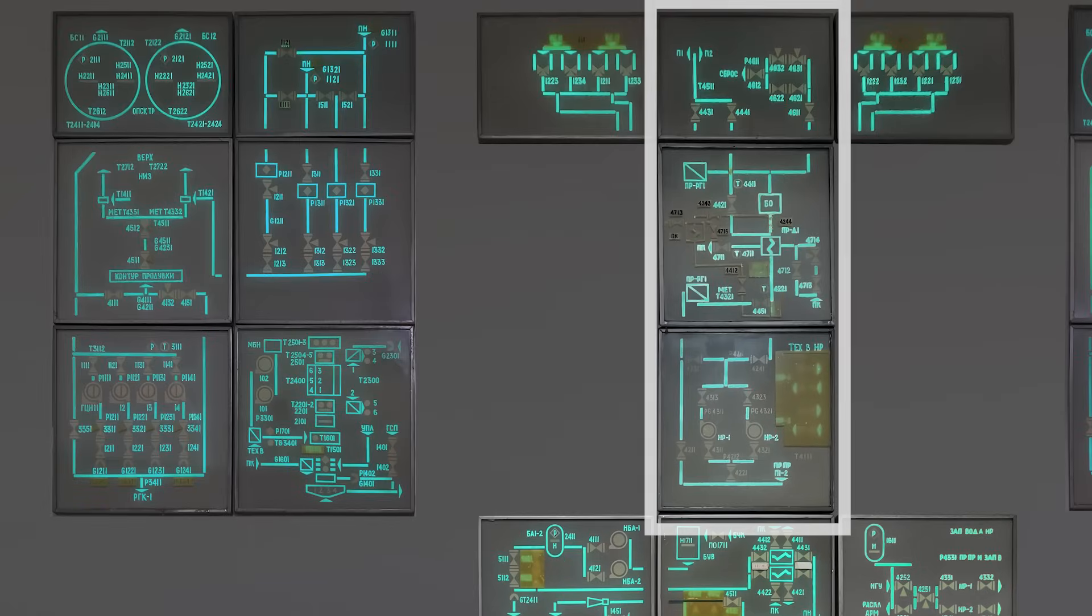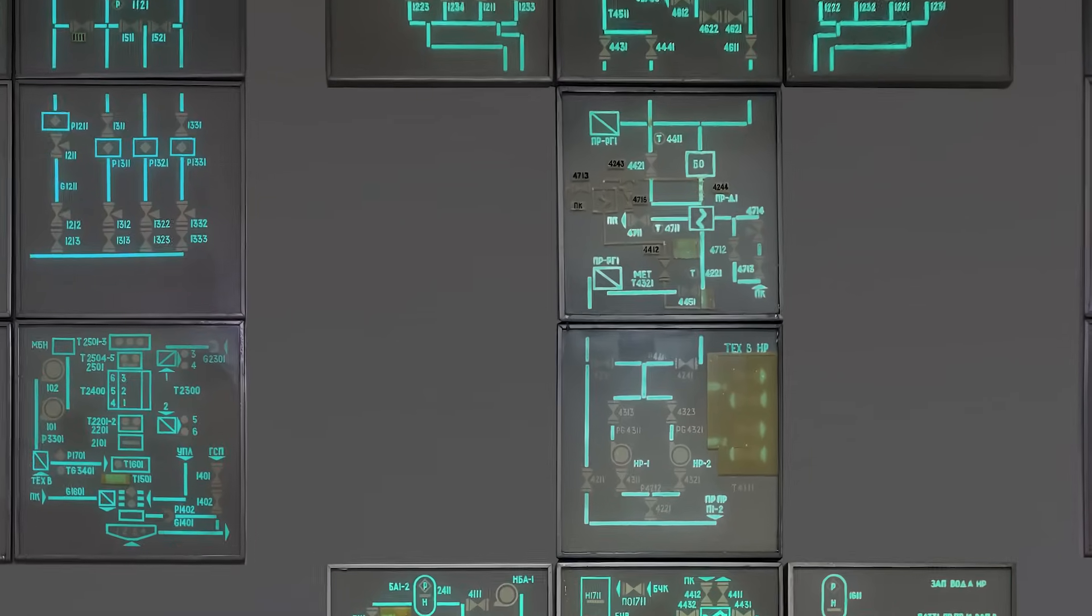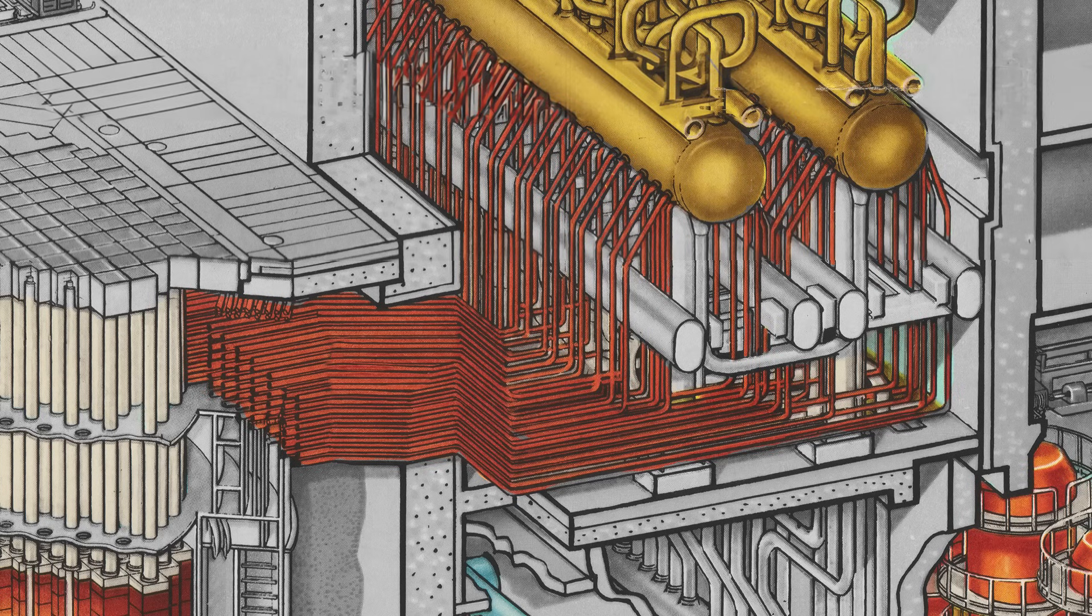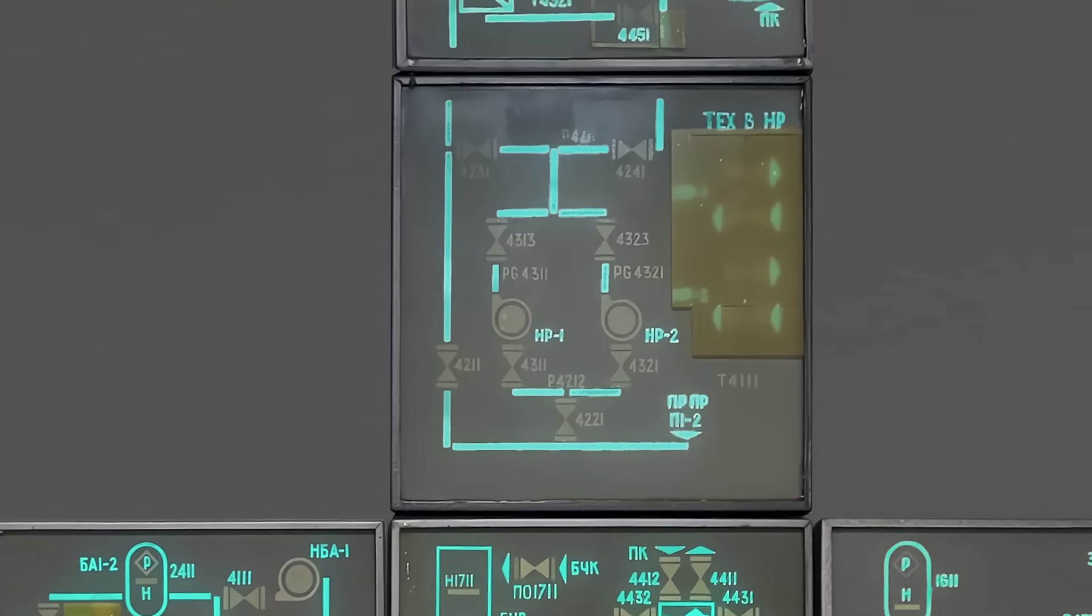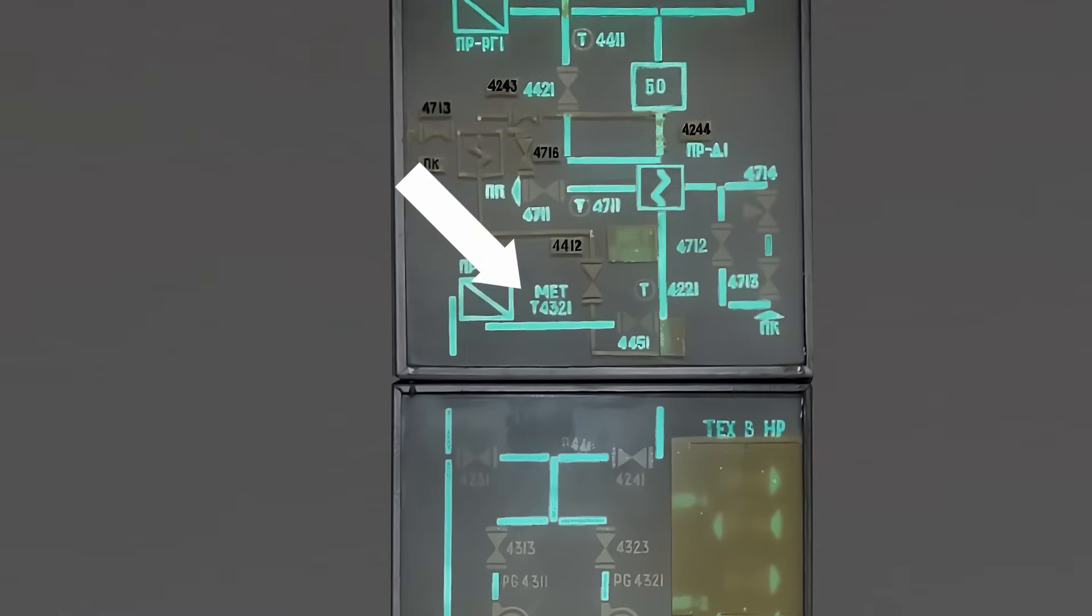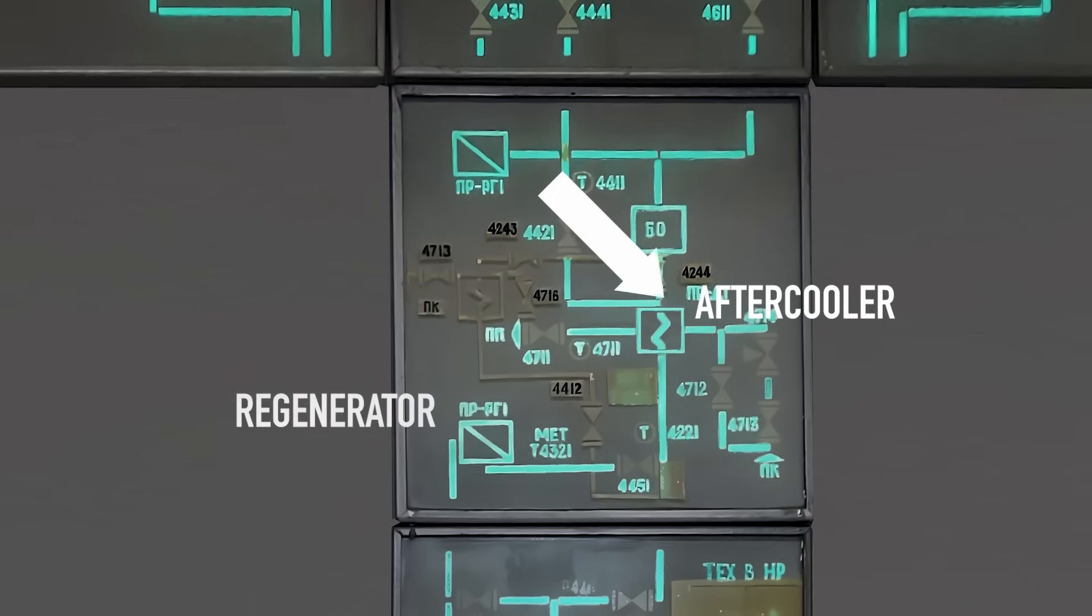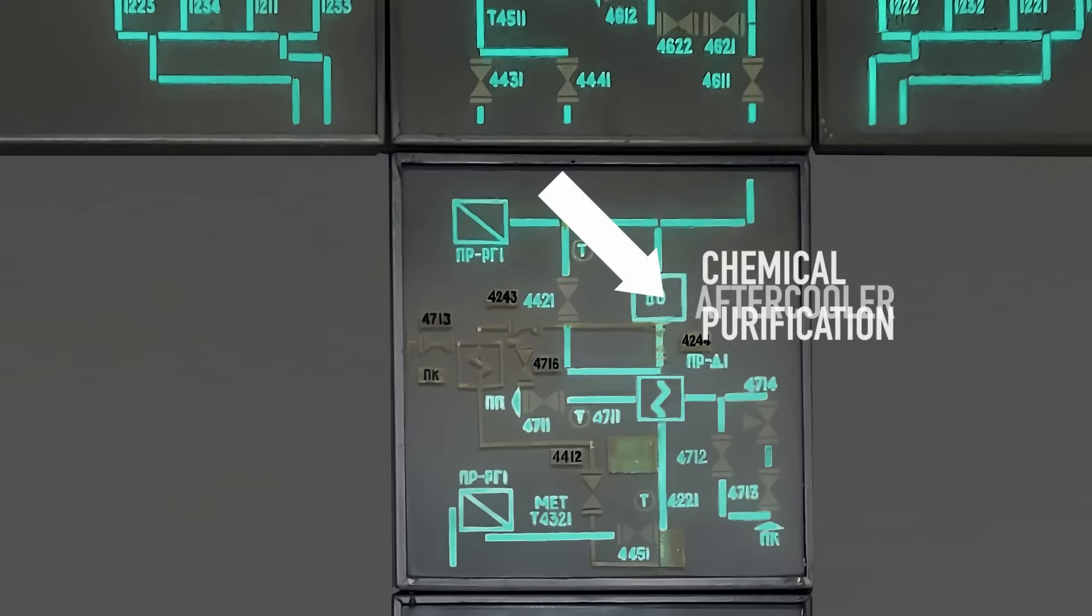Finally, there are these displays, which represent a very important part connected between pumps and drum separators. This is so-called blow-down and cool-down system, and it has two important functions. This part of the system purifies the reactor coolant. Why it has to be done? Because when it moves through the kilometers of piping all the time, it all the time will pick up chemical contaminants which is not good for the efficiency of steam and for the integrity of systems. So here it is collected and passed through a regenerator and then an after cooler, so that gradually reducing its temperature. Then almost cold it goes through a purification unit and then returns to drum separators.